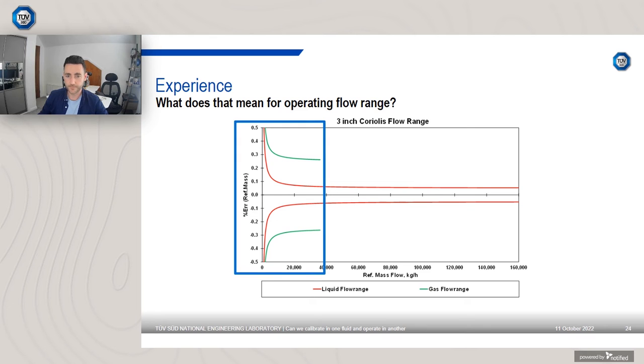So again, just highlight them with my blue rectangle. You can see liquid up to 160,000 nominally, but gas was only up to, I think it was around about 36,000. So a notable difference. Now, you might think, well, that doesn't matter too much, but it does if you're trying to calibrate it in water for gas use, because what flow rates are you going to calibrate the device?